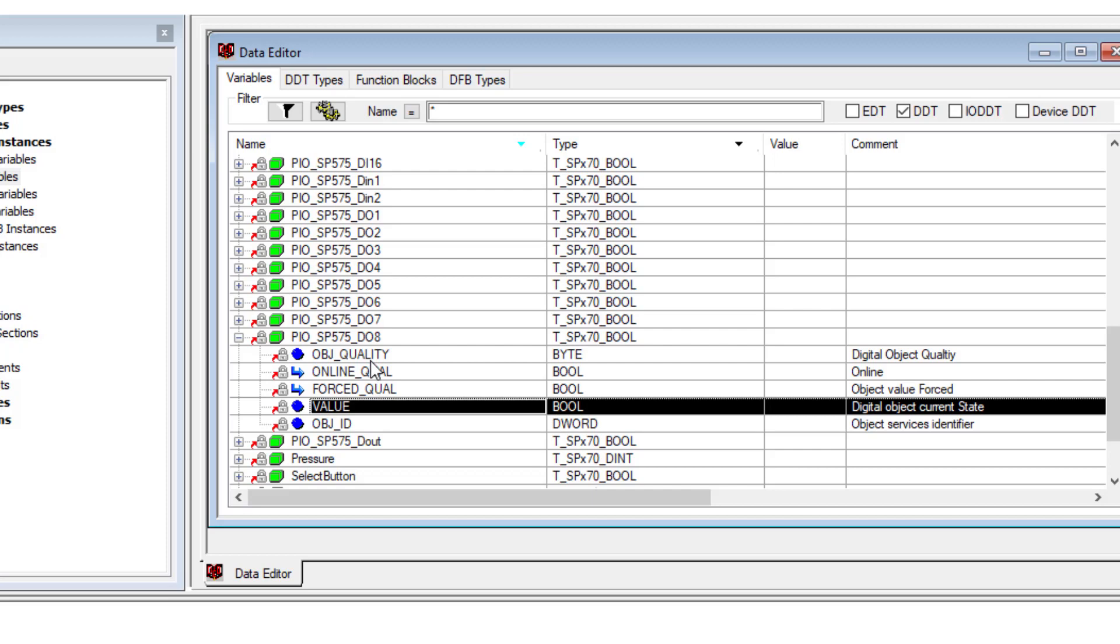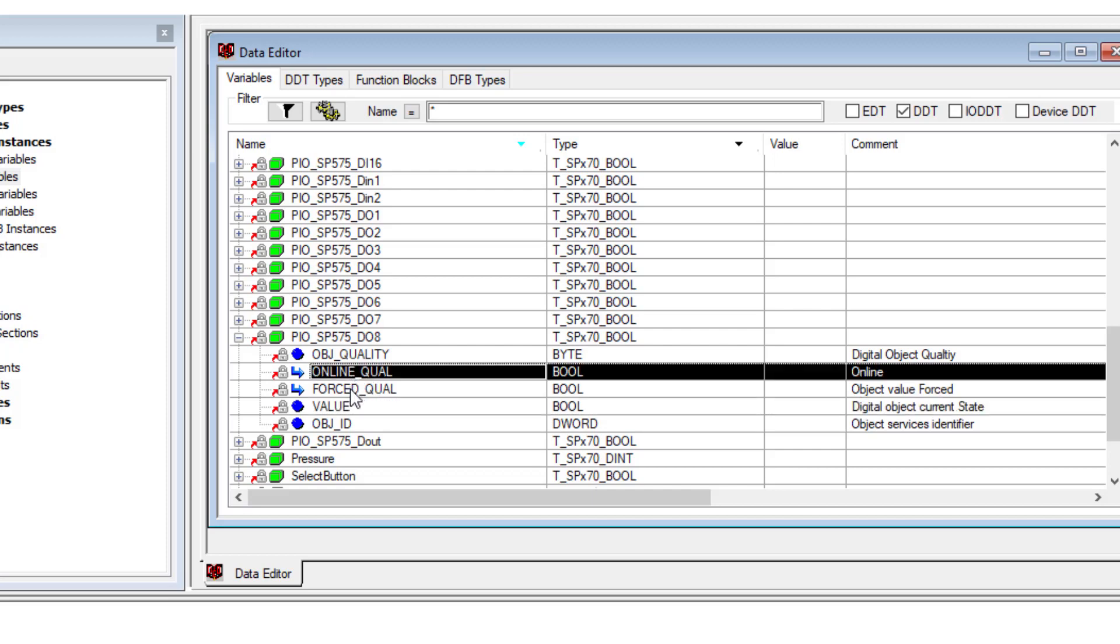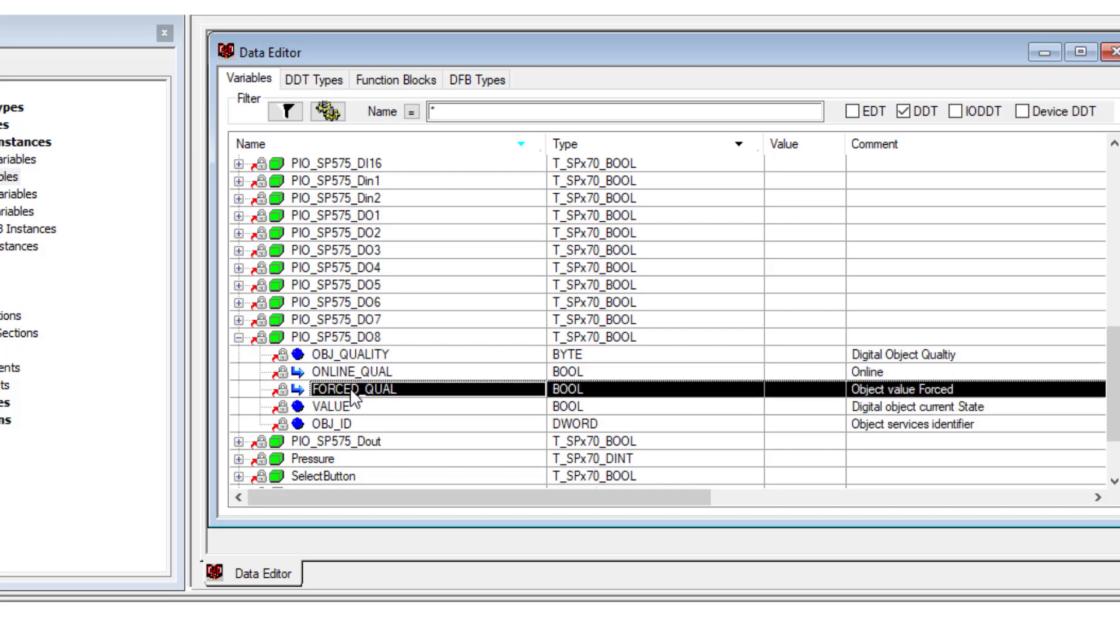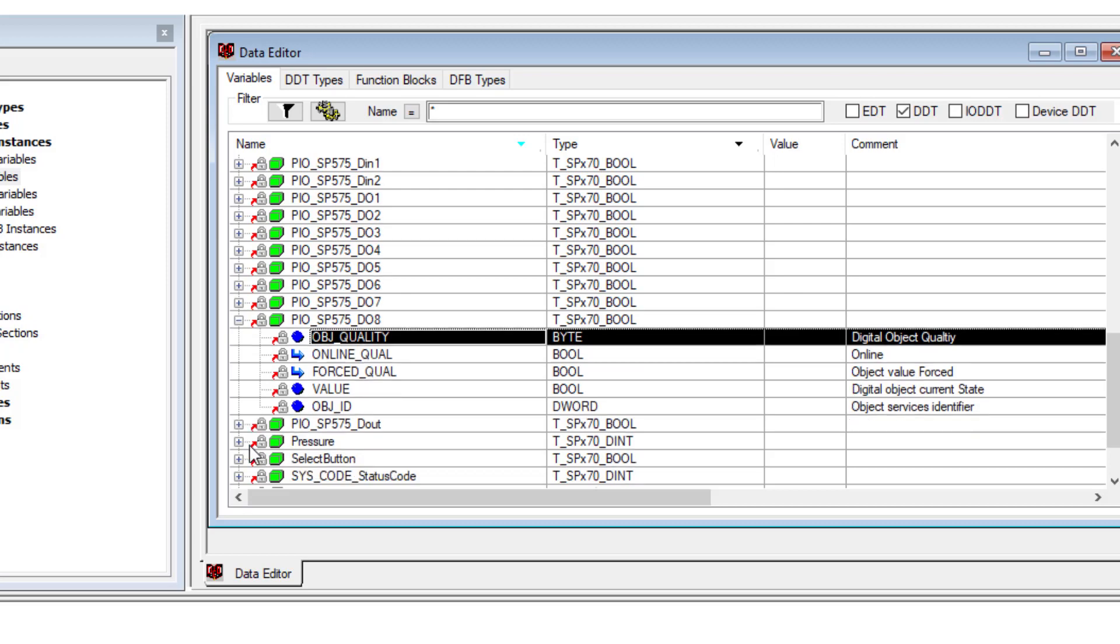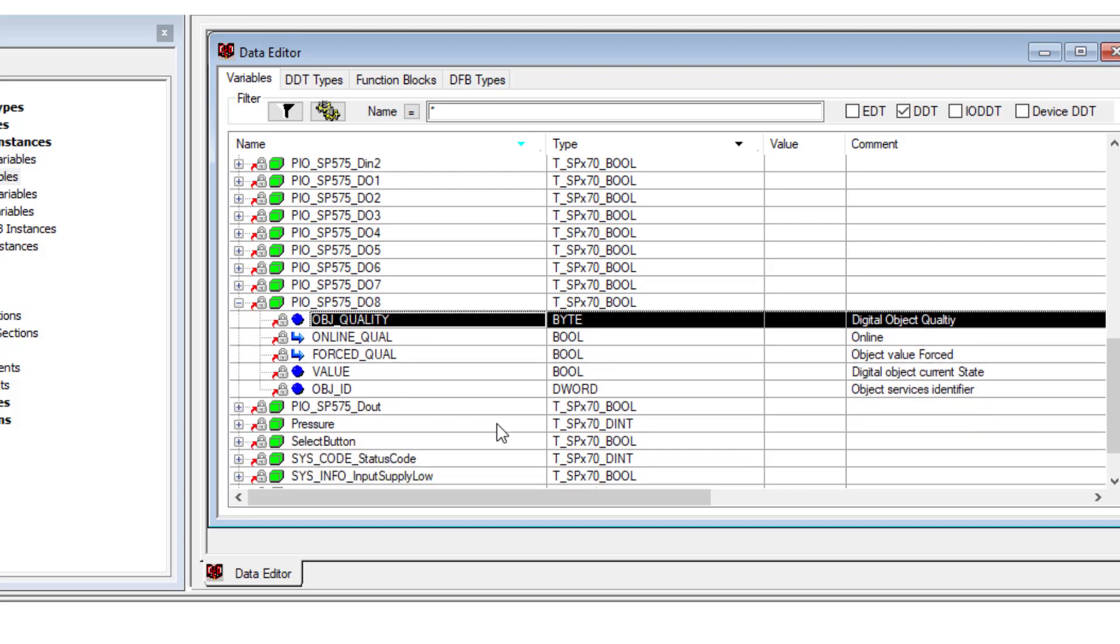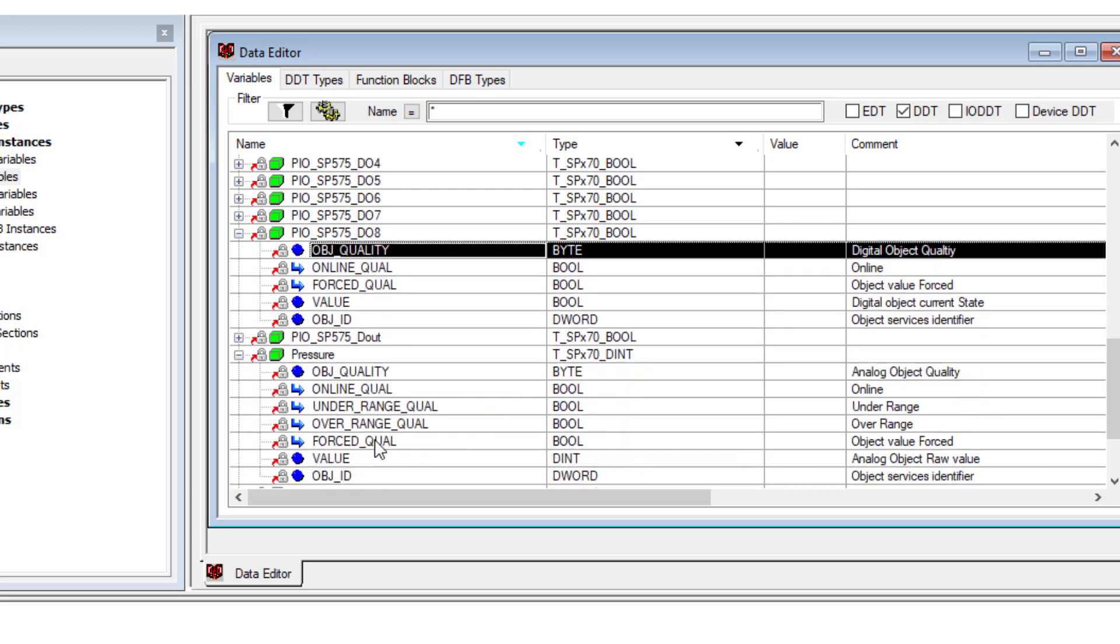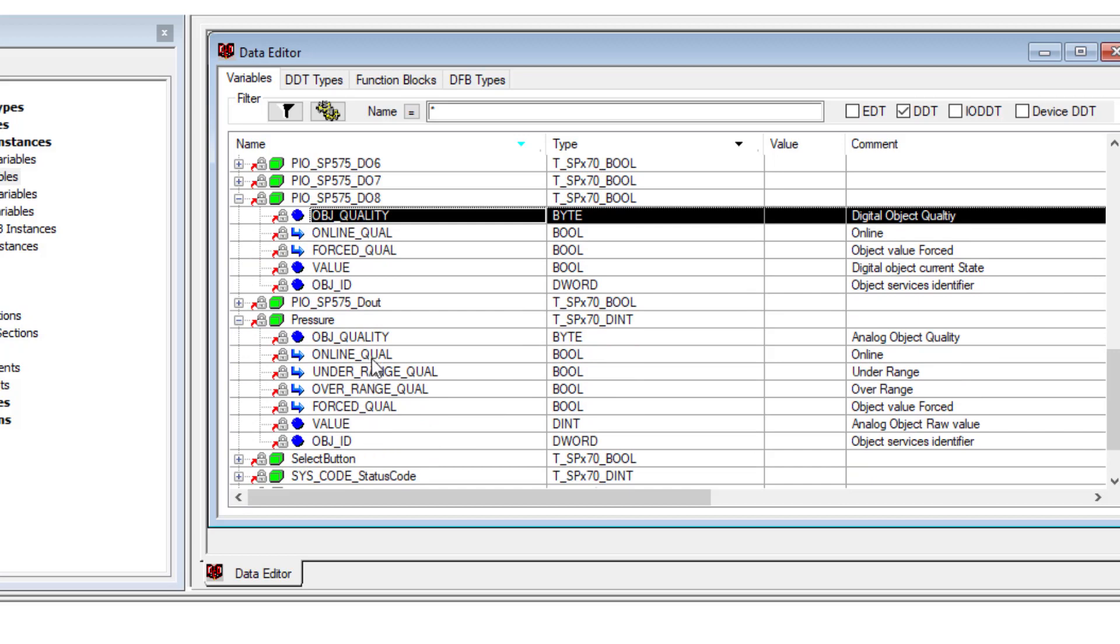Not only is the boolean value exposed to logic, but also the quality properties. Like whether it's online or forced, and you can look at all those properties as a byte for quality. What about for an integer? We have the pressure as an integer. Now we have in the quality byte the individual bits of online or offline.